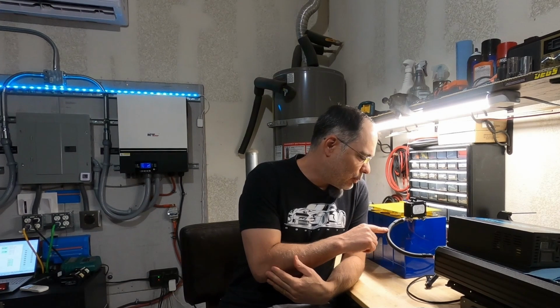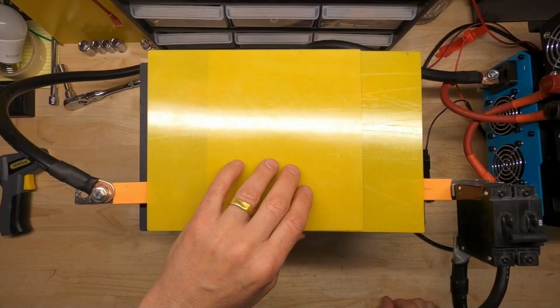Yeah, so a couple of you mentioned that the 50mm cable going from the breaker to the BMS cannot handle 200 amps continuously. A 48 volt battery at 200 amps, that's 10,000 watts. That's a lot of power. I don't know who's using a single battery with 10,000 watts continuously. But that's what they say and claim that it's rated for. So I figured, let's try it out. Let's see if it can actually do it. So let's take a look at the test setup.